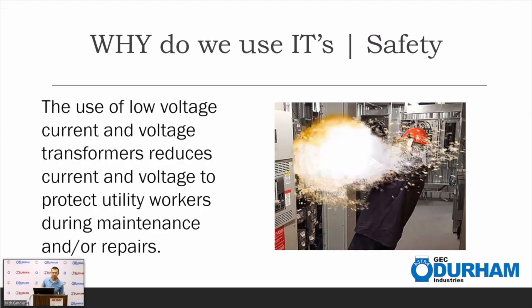One of the whys of instrument transformers is for safety reasons. Obviously, whenever you can reduce the voltage down to much safer levels from 277, 480 down to 120 or 208, you're going to keep a lot of your utility workers and metermen much safer.